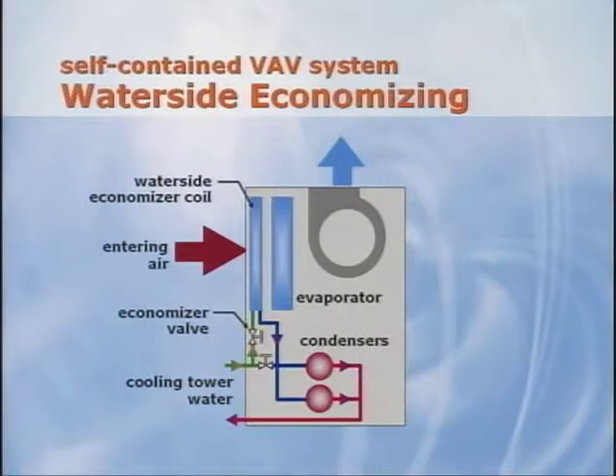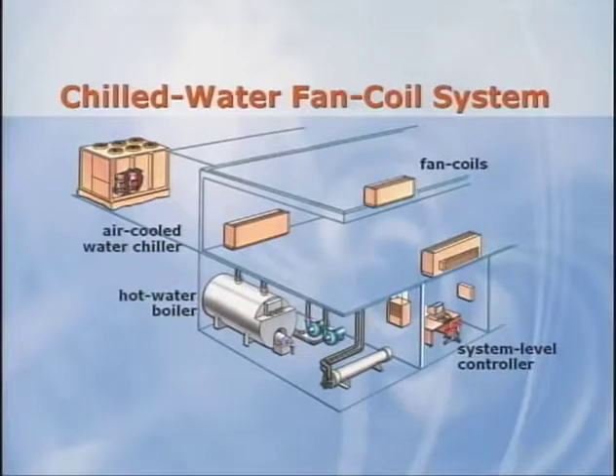This cool condenser water is used to pre-cool the entering air, reducing the cooling demand on the refrigeration system and saving energy. All right, what's next? The next system type is a chilled water fan coil system. Chilled water and hot water are produced at a central location and pumped throughout the building to individual fan coil units that are installed in or near each zone. A dedicated outdoor air system is used to condition all of the ventilation air and then divert it either directly to each zone or to each fan coil unit.